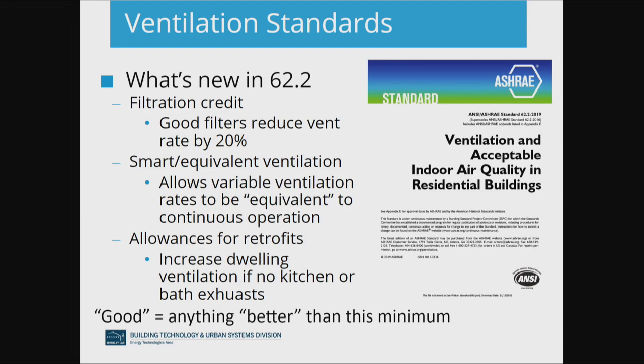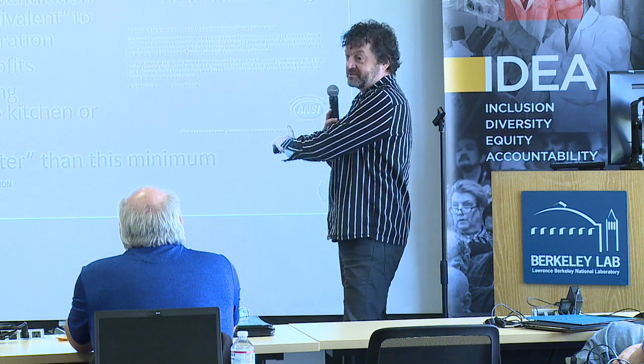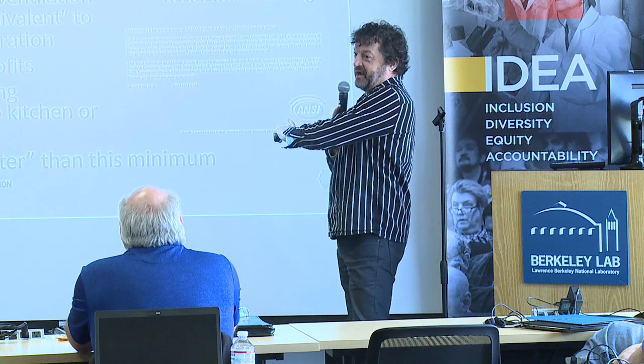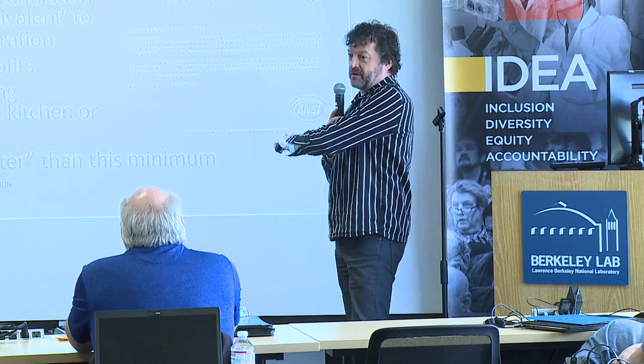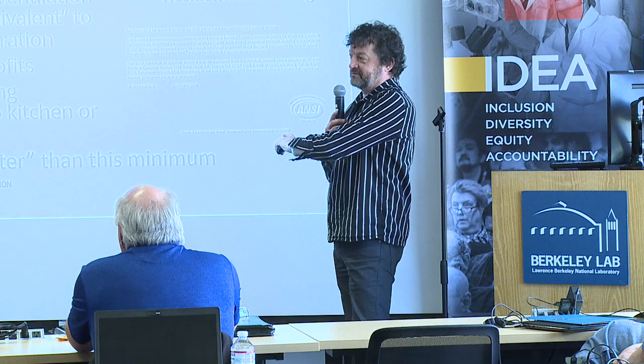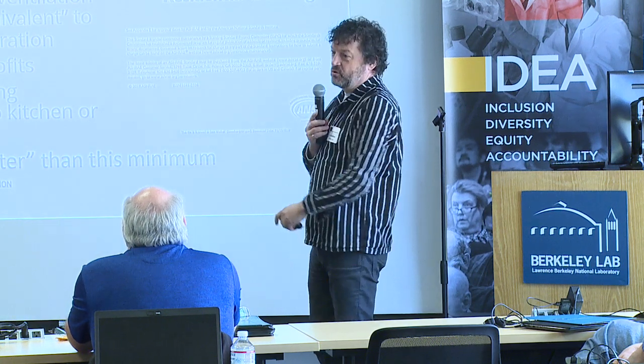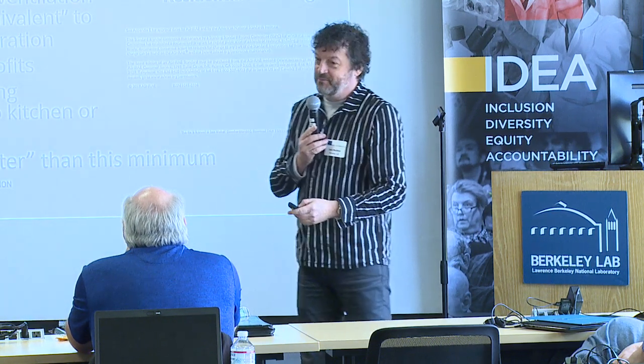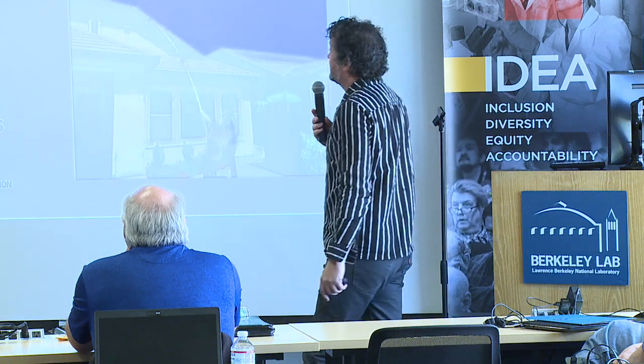But I want to emphasize, whenever you look at this standard for homes, or ASHRAE 62.1 for all the other buildings and spaces, these are minimums. It's just the worst, and I emphasize this because people get confused all the time. People think that this is best practice. This is the opposite of best practice. It's legally the worst thing you can do without getting sued. That's not best practice. So anything you can do better... but this just says what's the minimum. You're laughing, but this happens all the time.